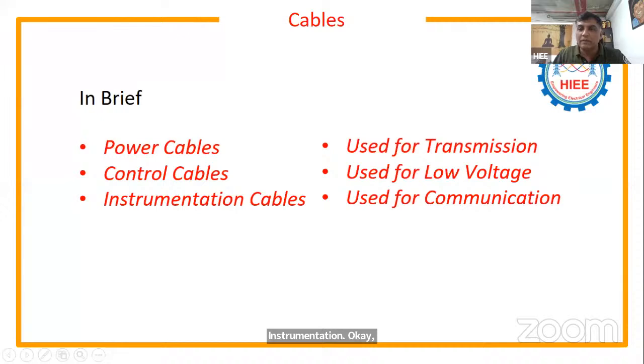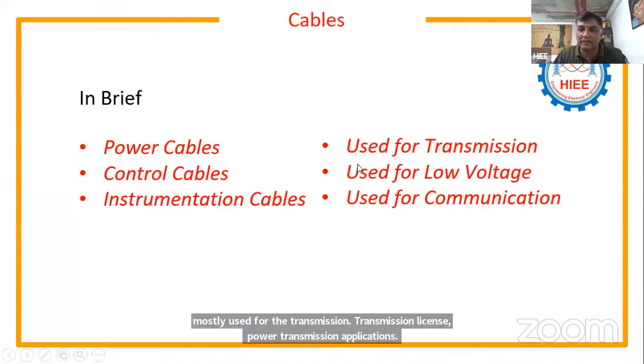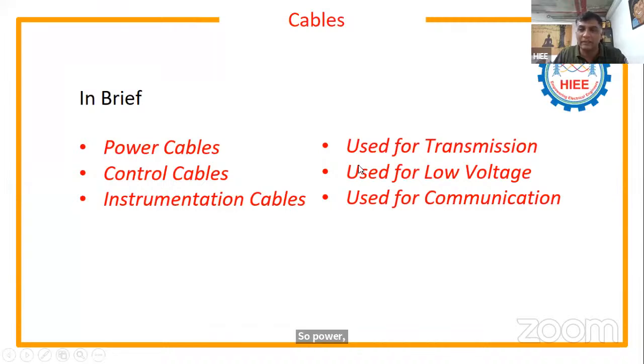Generally, power cables are mostly used for transmission, in the sense of power transmission applications. So power feeders, like three-phase or single phase, whatever it is. Control cables are used for low voltage control applications with a voltage of 110 volts and 220 volts. And instrumentation cables are used for communication, and PLC and SCADA applications. Generally, instrumentation cables will be multi-pair cables, like 10 pair, 20 pair, something like that.